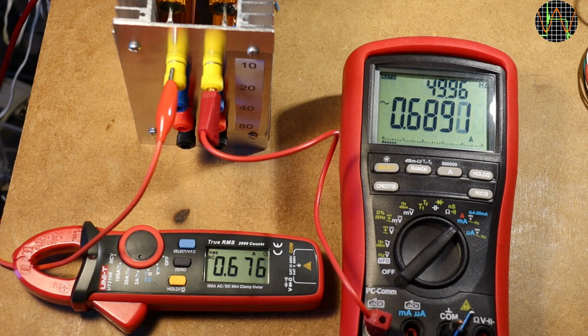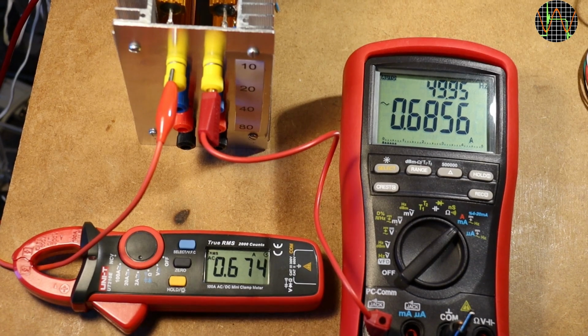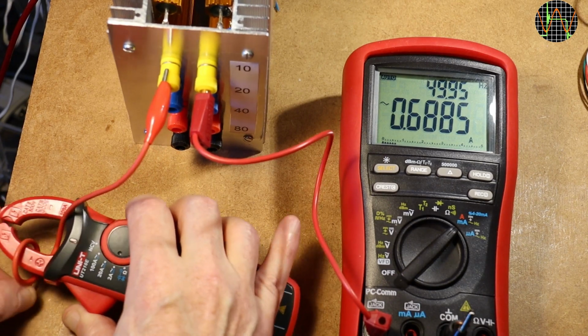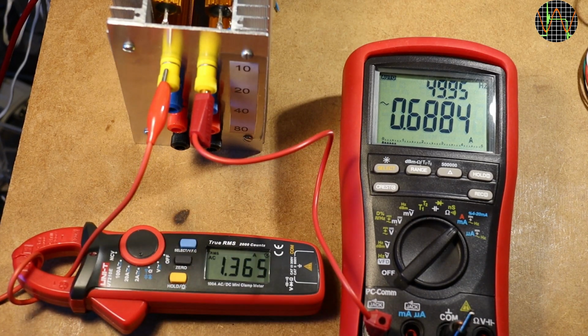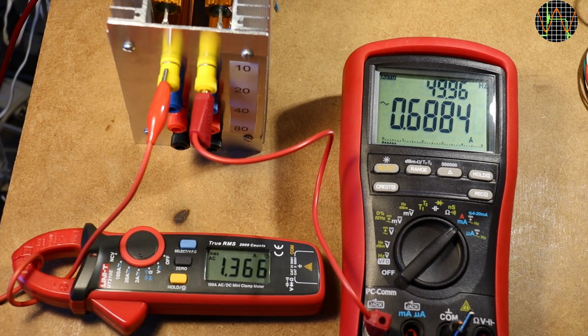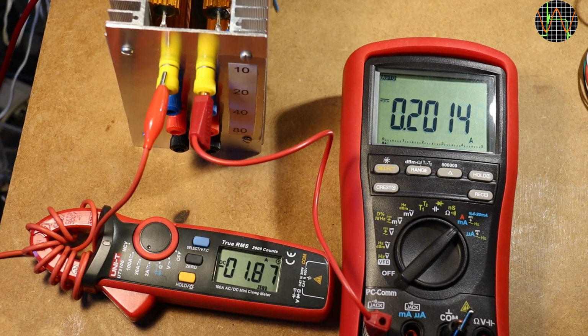To see if the Hall effect sensors of the UT210E fall for the same trick, I measured a moderate current through a single wire, about 0.68 amps. Now I make a loop so the same current goes twice through the UT210E clamp. And sure enough, the display is now double, even though the current is still the same. So here's my test setup to measure the DC 20 amp range. It's basically a repeat of the 2 amp test, but the wire carrying the current loops 10 times through the UT210E clamp, so when the BM869S reads 1 amp, the UT210E should read 10 amps.